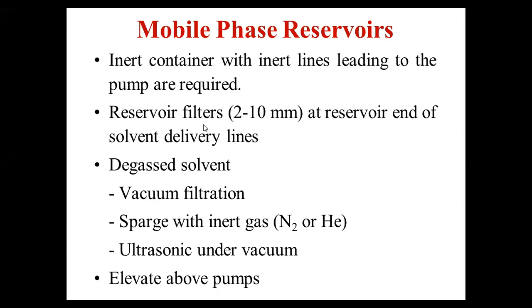And reservoir filters will have the capacity to remove 2 to 10 micrometer particulate matters, because the mobile phase must be free from any particulate. And the degassing system is provided with vacuum filtration or purging with either nitrogen or helium gas. What I have shown you is purging with helium gas. Ultrasonic purging will also be done under the vacuum system.